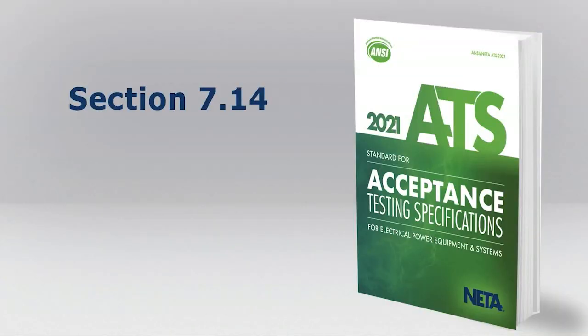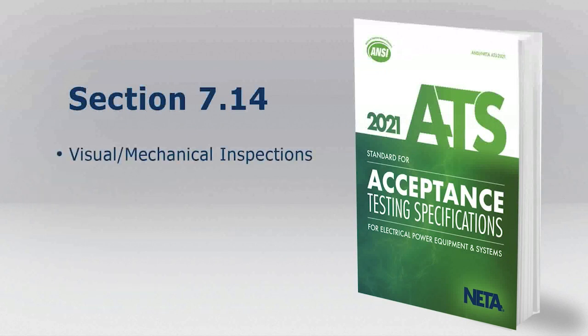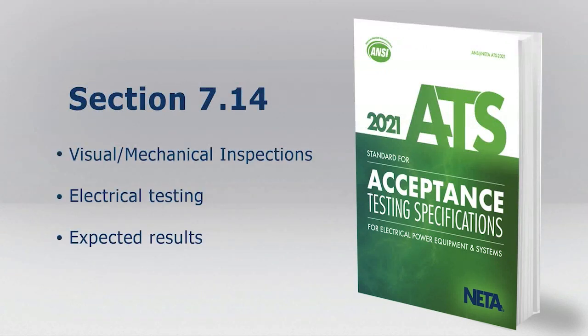And so how do we test this in the field? We use the NETA testing standards. If you go to section 7.14, it tells you exactly what you need for that ground fault protection system. It tells you the visual and mechanical inspections, it tells you the electrical tests, and then gives you the expected results. So NETA gives you a very comprehensive set of tests and inspections that you can follow pretty simply through the standard. Let me point out a couple of important ones.